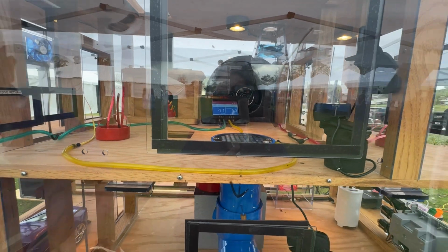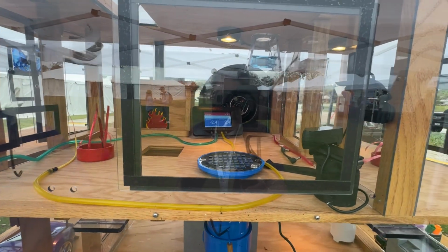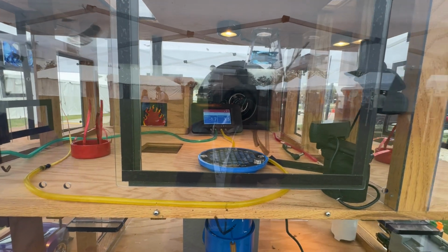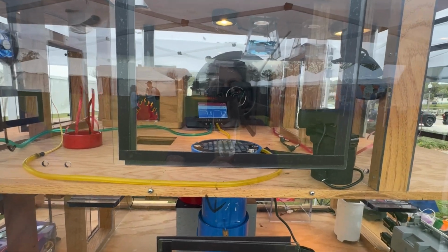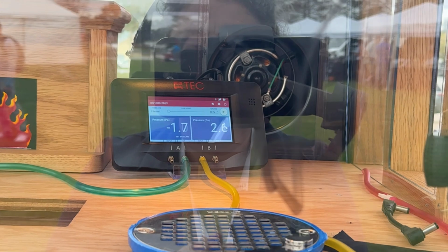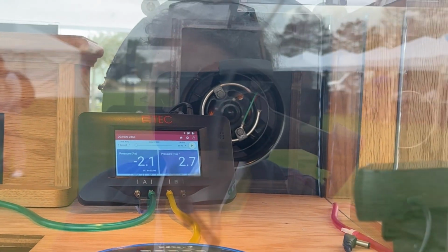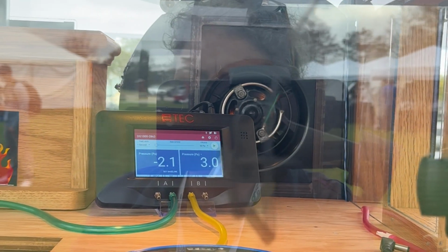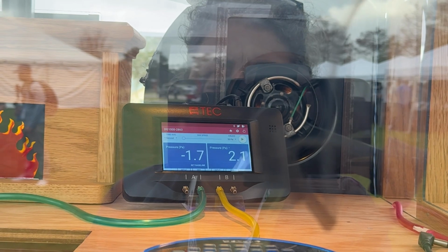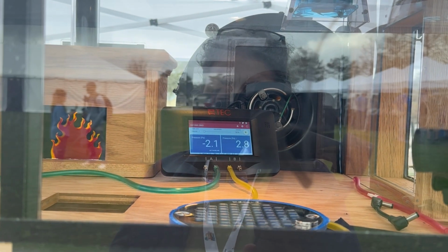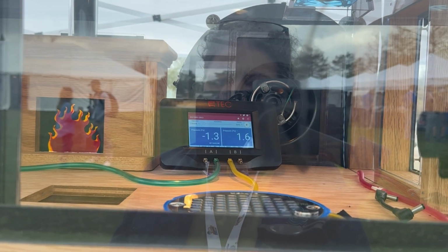So what we'll do is use a tool called a roomulator. Basically, you're trying to figure out how big the gap is that you made when you open the door, in other words, how many square inches that is. Then you can design a duct to jump over the wall, go through the wall, or sometimes add a return directly to that room.